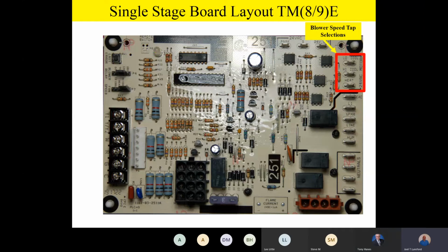Very good, thank you. Okay, team, right below that, below our motor speed taps, we have 120 volt output. It's an EAC, that's for an electronic air cleaner. And please make a note of this, that EAC will be energized anytime the fan is running. We'll have 120 volt output to run an electronic air cleaner. Right below that, we have a L1, and what that is, that's an input to the board for 120 volt components.